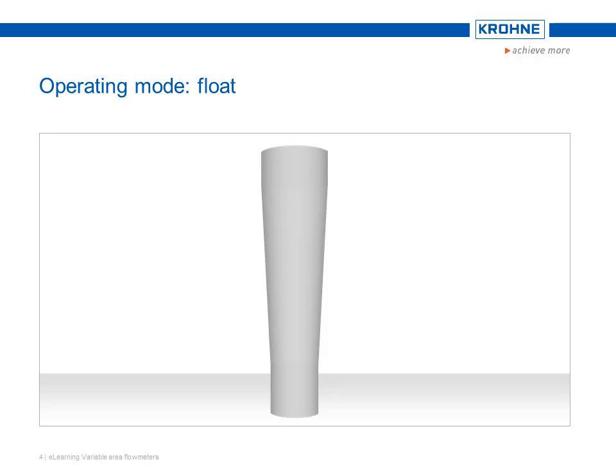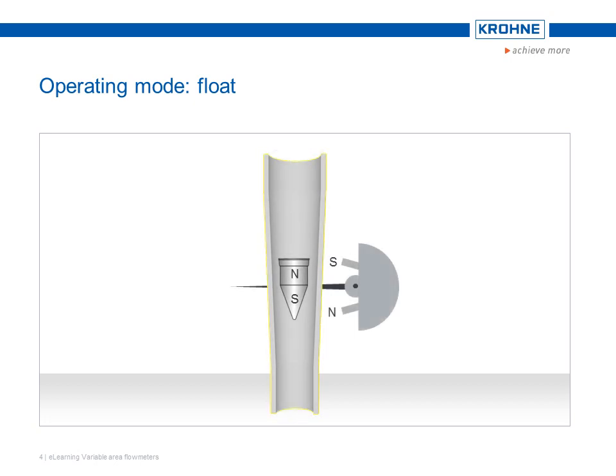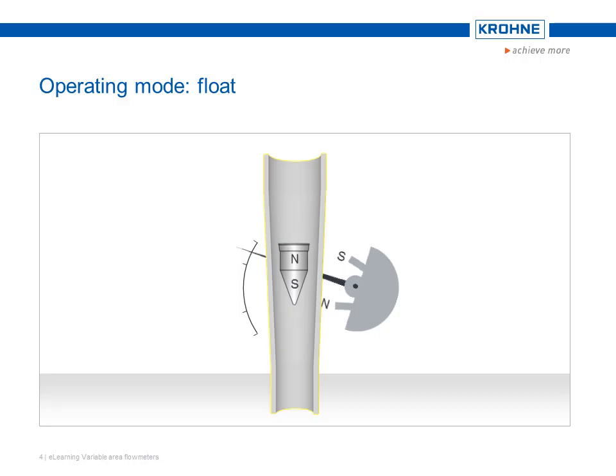With metal cones, the float is not visible, so they have a magnetic transfer onto the pointer. For this purpose, a magnet is built into the float. Through a magnetic coupling installed on the pointer axis, the linear movement of the float is converted into the rotary movement of the pointer, which displays the flow on a scale.